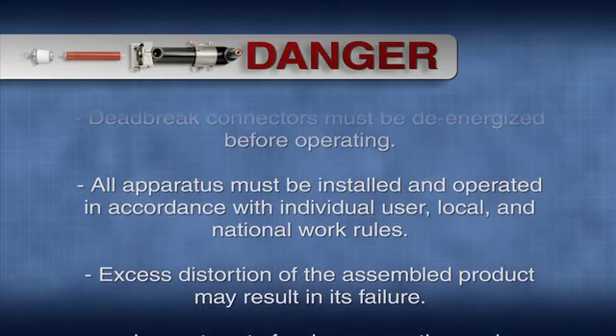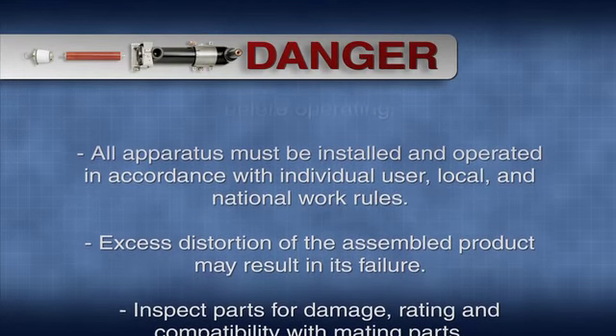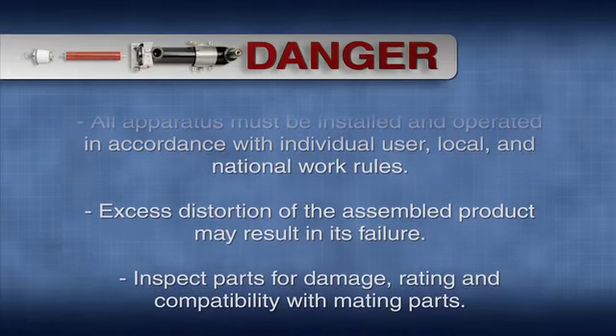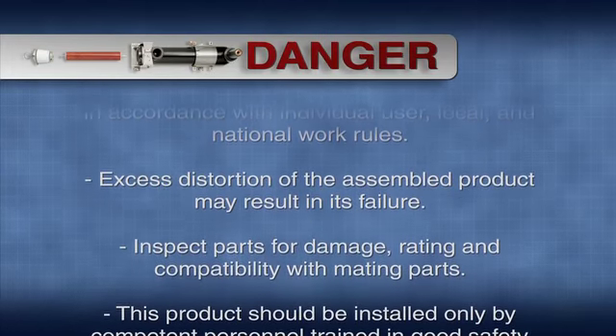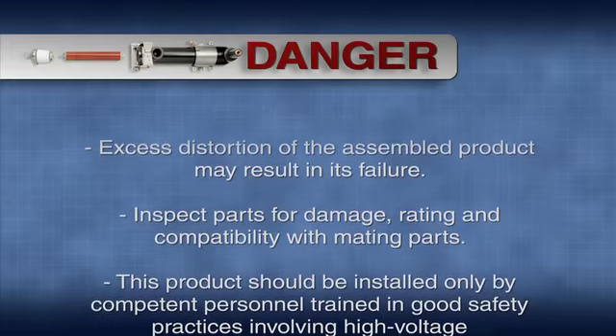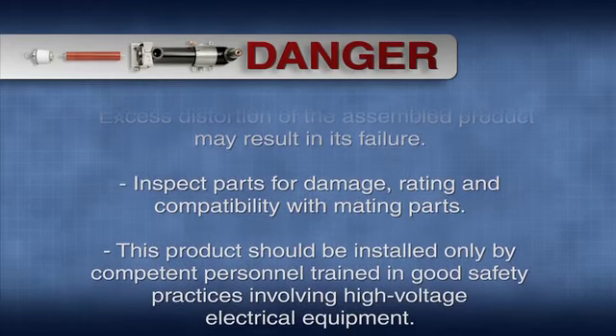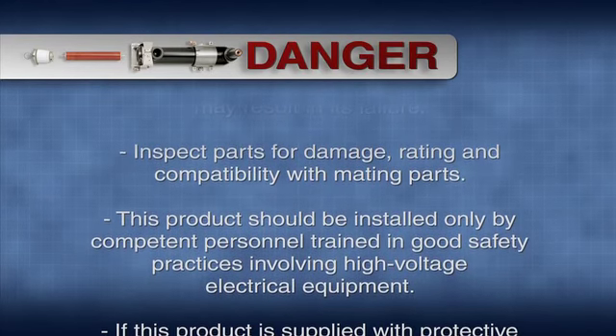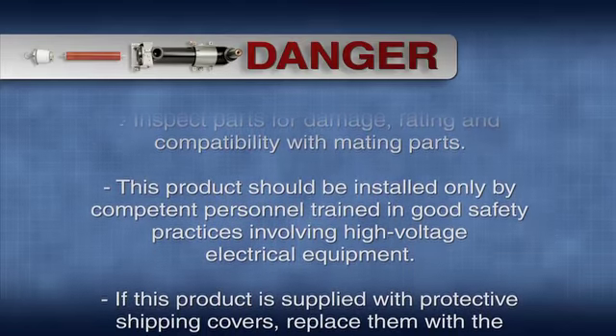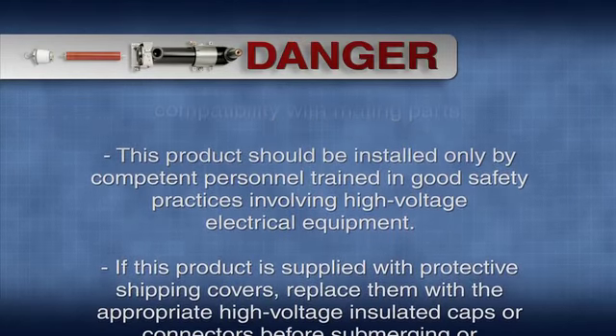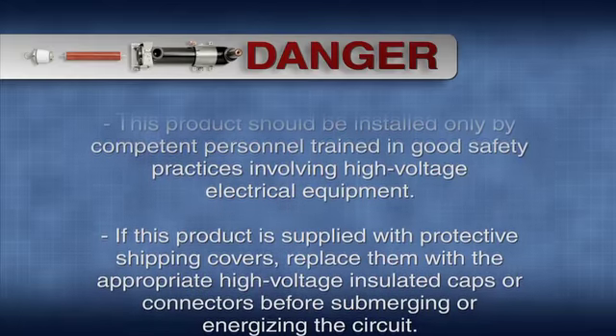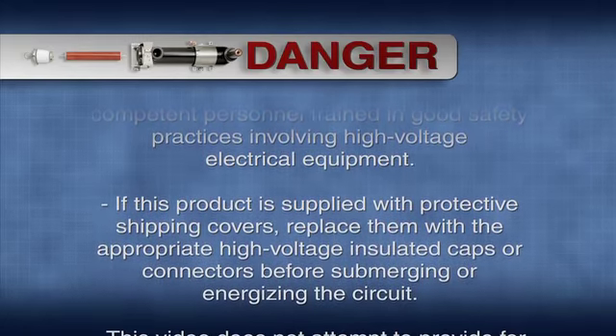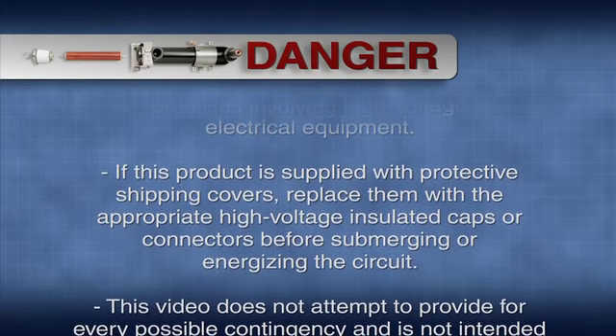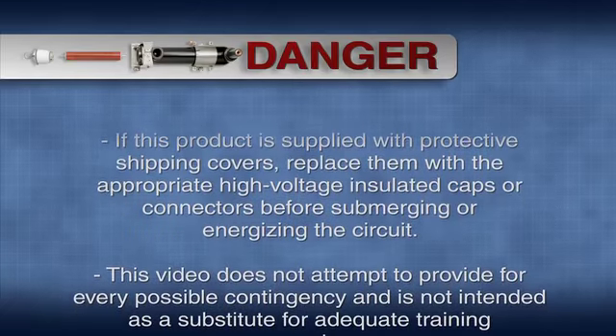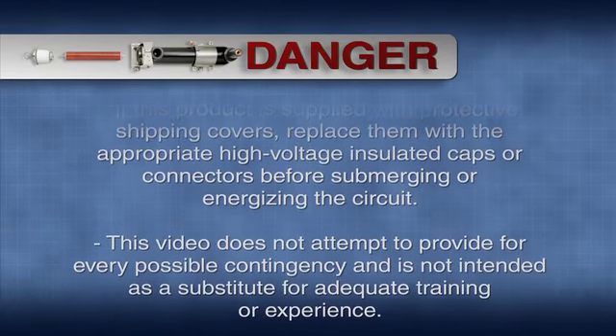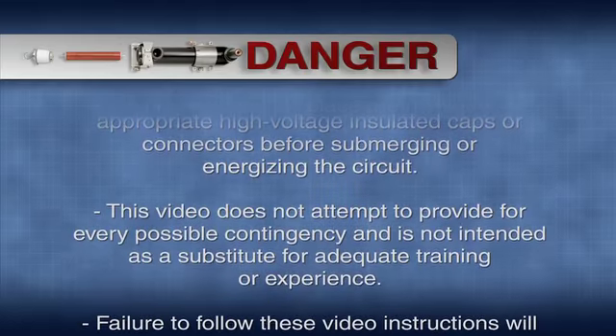All apparatus must be installed and operated in accordance with individual user, local, and national work rules. Excess distortion of the assembled product may result in its failure. Inspect parts for damage, rating, and compatibility with mating parts. This product should be installed only by competent personnel trained in good safety practices involving high voltage electrical equipment. If this product is supplied with protective shipping covers, replace them with the appropriate high voltage insulated caps or connectors before submerging or energizing the circuit.